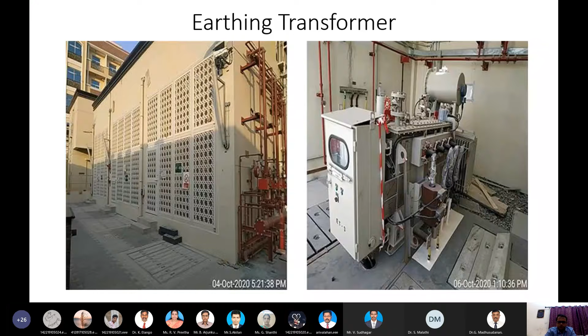The earthing transformer, as I said, is a feeder for the utility power recommended for the substations, for small powers. As I said, I don't want to repeat it again. It is a step-down transformer which converts the incoming 11 kV from the IDT to 400 volts for local utilization. So this is another step down from here.